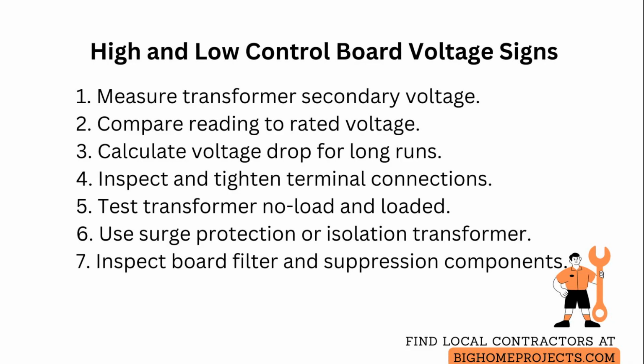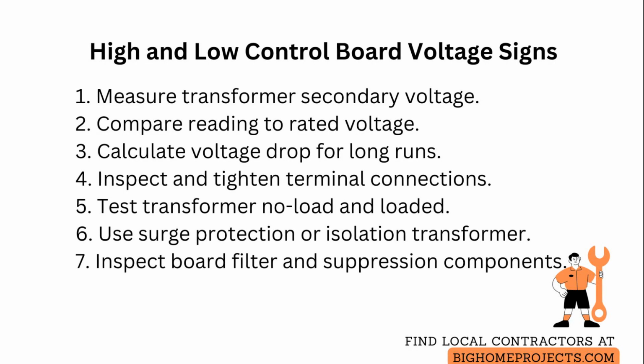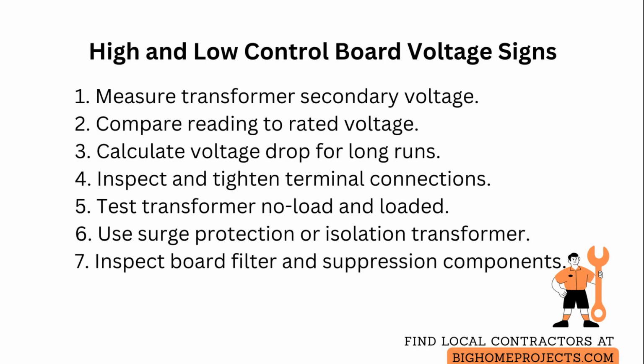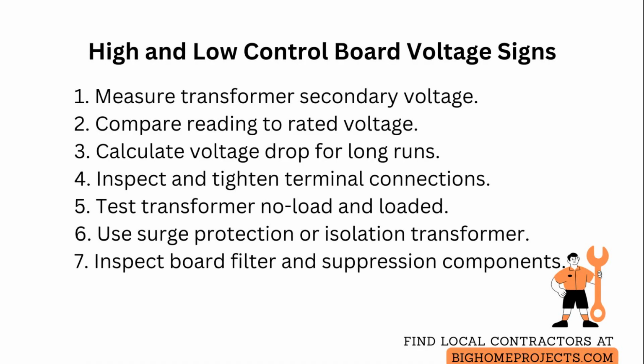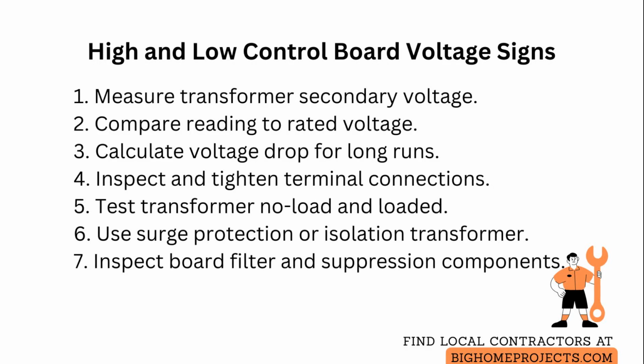So calculate voltage drop using the conductor resistance and load current and upgrade to a thicker conductor if drop exceeds 3% for control circuits. Check all terminal connections and splices for corrosion, loose screws, or signs of arcing. Clean, retighten, or replace terminals, and use rated crimp connectors or soldered joints where appropriate, because poor connections often create intermittent high-resistance paths that mimic low-voltage conditions under load.